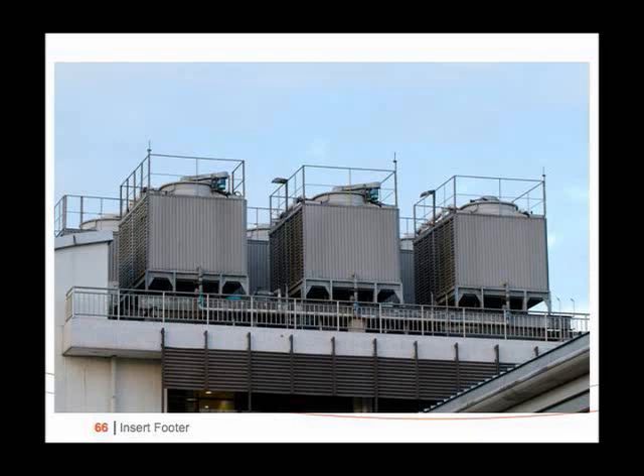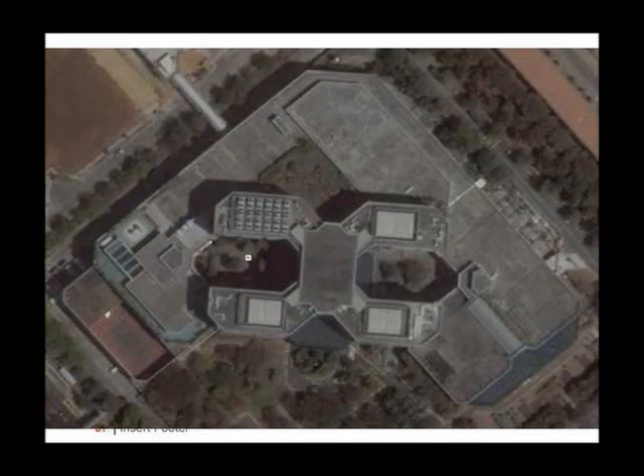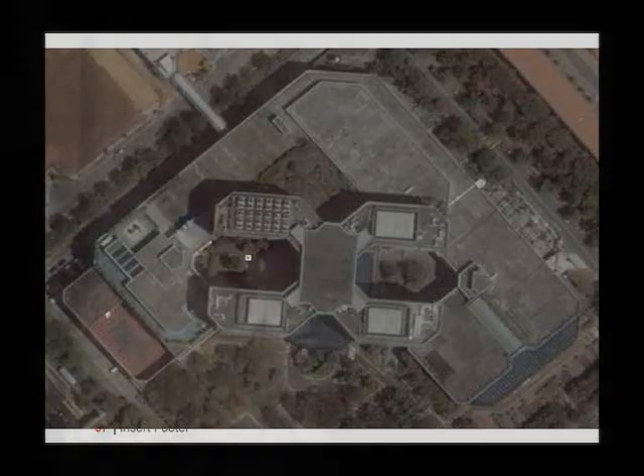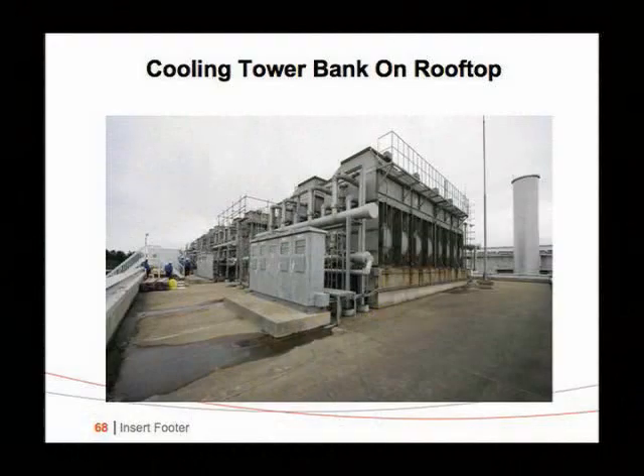Award-winning hospital, look at this. We have been there because these are train chillers and ridiculous temperatures. There's enough rooftop that they could have spread this out, but anyway. But it's not a uniquely Singapore problem. This is Japan. You look at this and you say, this is a bad selection. The efficiency of the cooling towers in terms of kilowatt per ton, you would never use it. Unless you are shareholders in a power station, you know, coal fire.